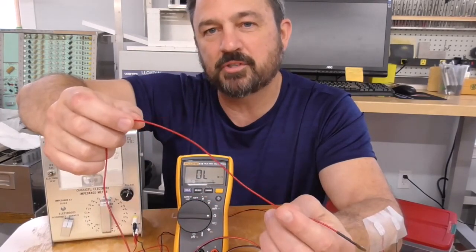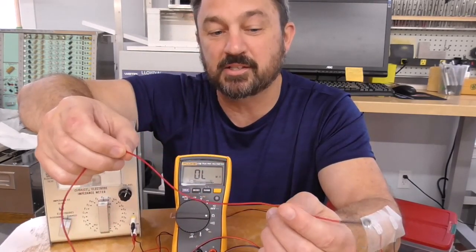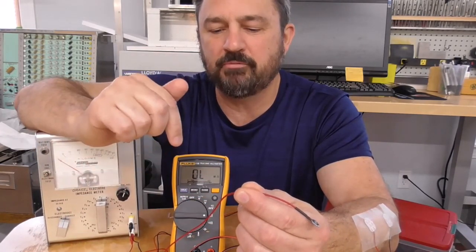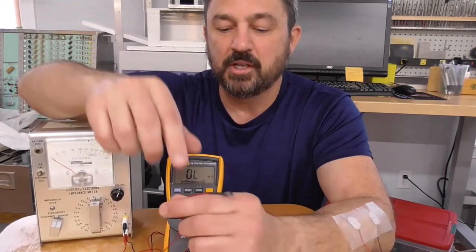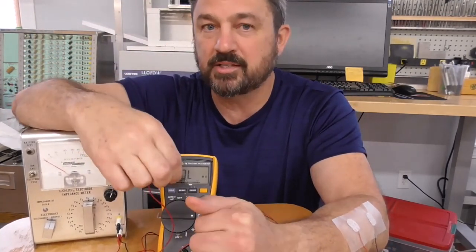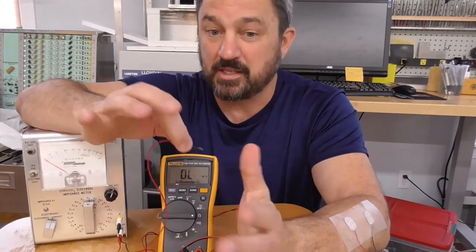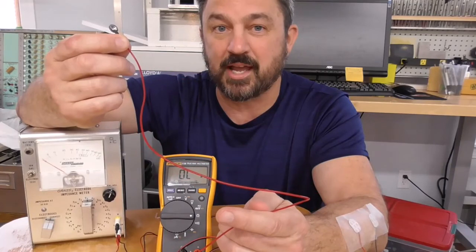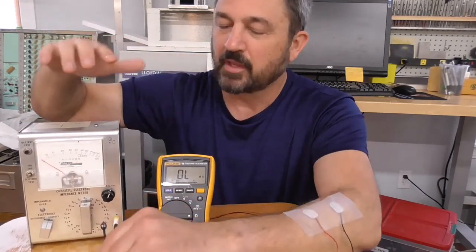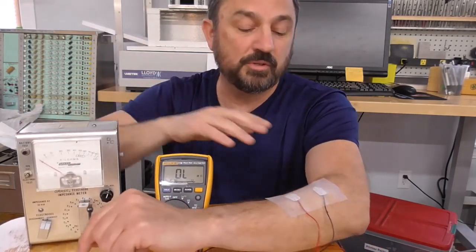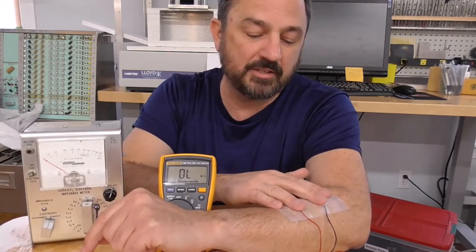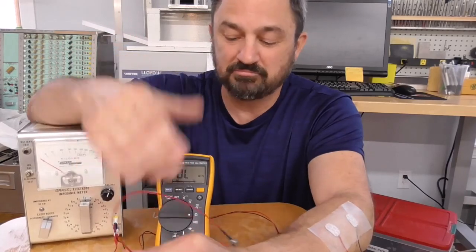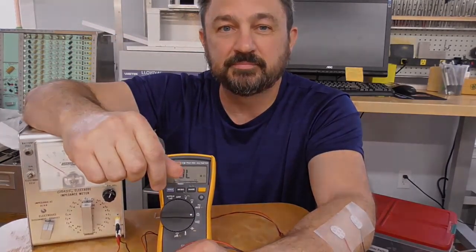Does that lead wire have some degree of capacitance and inductance? You bet. Would the impedance of this lead wire be different at maybe 1,000 hertz than the resistance value at a steady state DC voltage? Yes, it would be very different. But all we're doing is checking to see if our lead wire is intact. So in summary, the impedance meter must be used for measuring something that has tissue. However, checking to see whether our lead wires are intact, you can use an ohm meter.